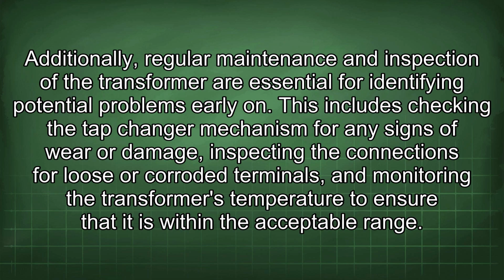Additionally, regular maintenance and inspection of the transformer are essential for identifying potential problems early on. This includes checking the tap changer mechanism for any signs of wear or damage, inspecting the connections for loose or corroded terminals, and monitoring the transformer's temperature to ensure that it is within the acceptable range.